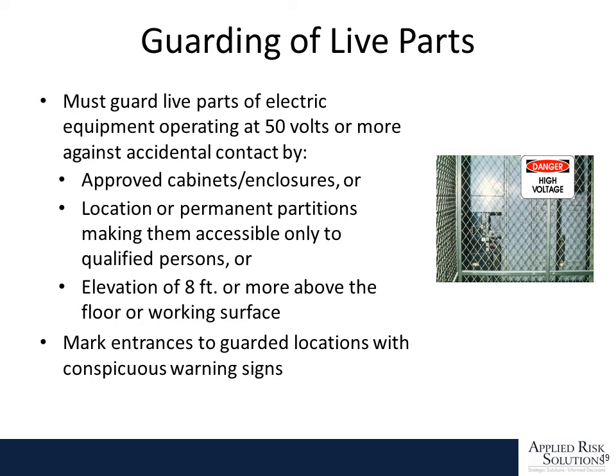Live parts must be guarded. On equipment, you must guard live parts of anything more than 50 volts. It must be in either an approved cabinet or enclosure, or located with permanent partitions to prevent somebody who is not qualified from gaining access, or it must be elevated 8 feet or more above the ground. Entrances should be marked with signs stating high voltage.